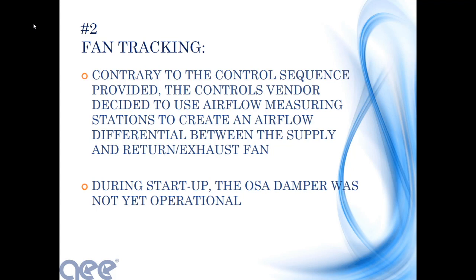In this particular example, the control contractor, the vendor, decided he would ignore the sequence that we gave him for tracking a supply fan and a return/exhaust fan. Because the air handling unit that was provided had these flow measuring pitot grids at the inlets to the fan, being the controls guy that he was, he said, well, I'm going to measure airflow directly, and I'm going to maintain a differential of airflow between the two fans.